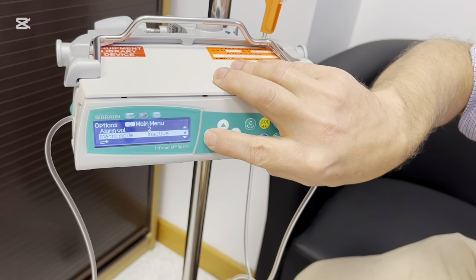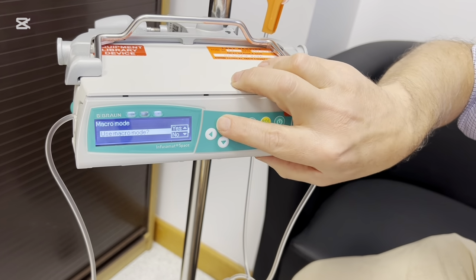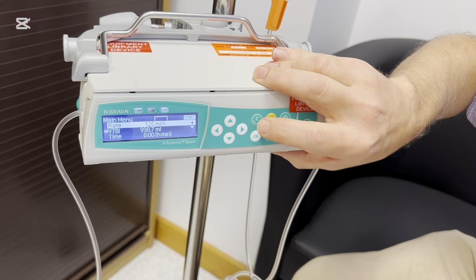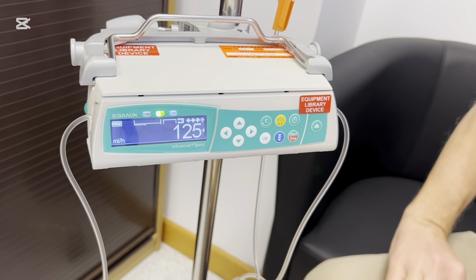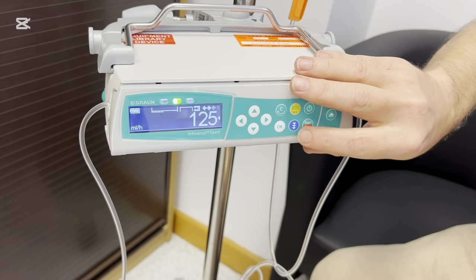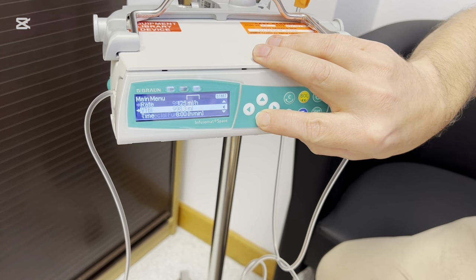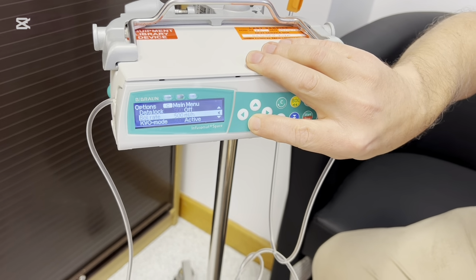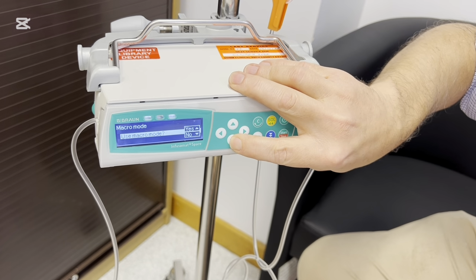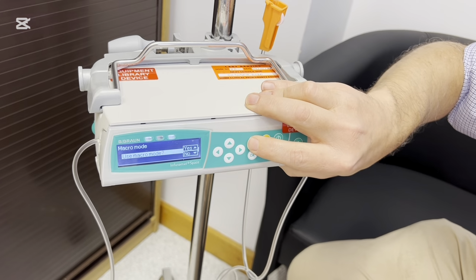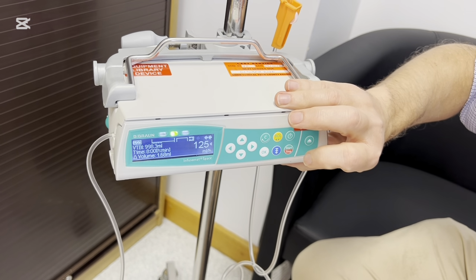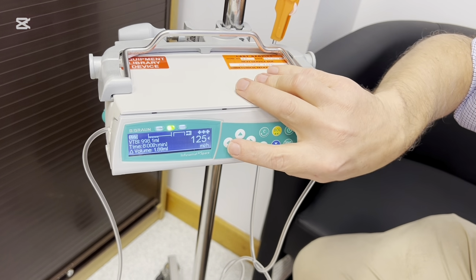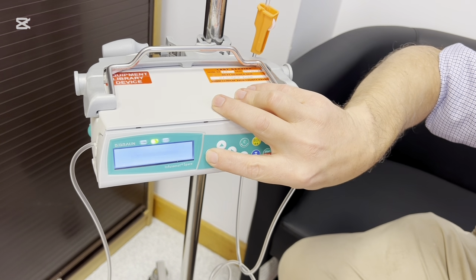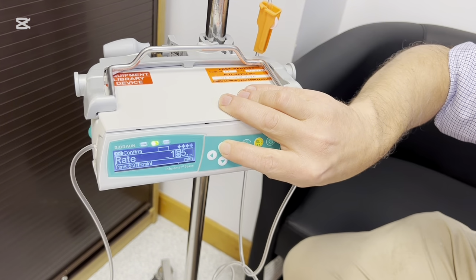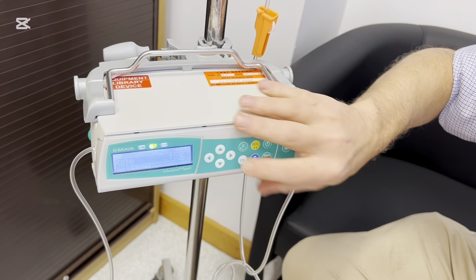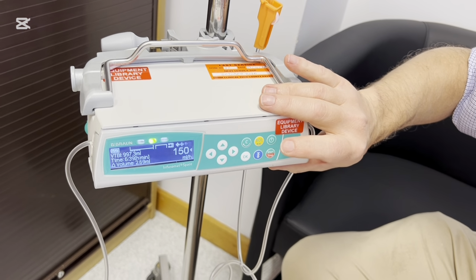We can have bigger numbers, so you can see the numbers from a further distance. Go back to the normal size screen. And what we can do on here is we can do what we call a running rate change. So if you just press the button to enter the menu, I'm going to select that number, press OK, and just change the rate without having to pause the pump and enter the menu and then restart the pump.